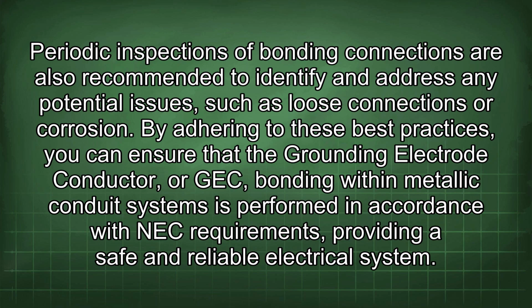Periodic inspections of bonding connections are also recommended to identify and address any potential issues such as loose connections or corrosion. By adhering to these best practices, you can ensure that the grounding electrode conductor, or GEC, bonding within metallic conduit systems is performed in accordance with NEC requirements, providing a safe and reliable electrical system.